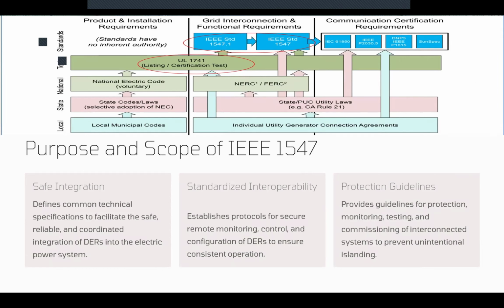So the first purpose of this standard was to have a safe integration. Okay, what does that mean? The objective is to make sure that the DERs can interconnect without compromising the safety or reliability of the utility personnel, customers, or equipment. Okay, so the key aspects are defining uniform technical specifications, so all the DERs, regardless of their manufacturing system or the manufacturer, follow the same electrical interconnection rules. This also includes some strict anti-islanding requirements, so we could protect the line workers during outages. So DER must disconnect quickly if a portion of the grid becomes de-energized.